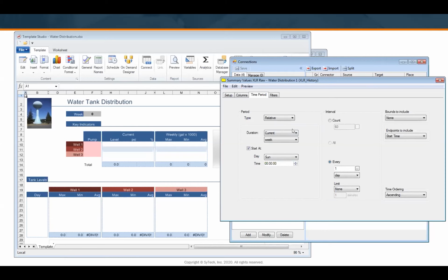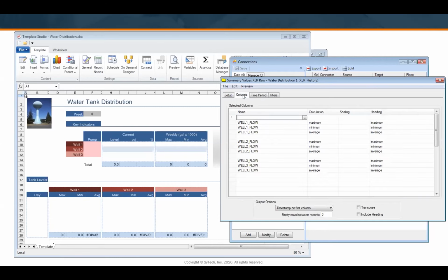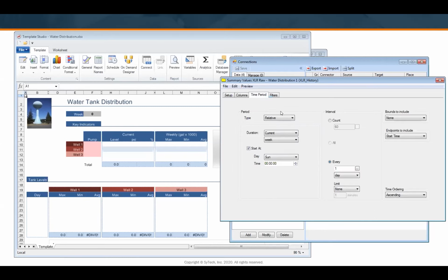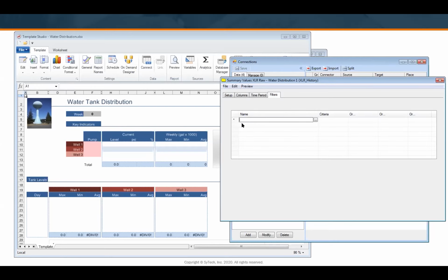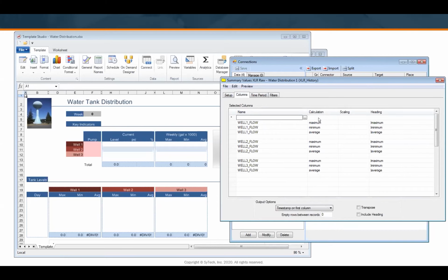Now, also, when you're calculating min, max, and averages, the worst thing you want is to include values when your pump wasn't running, because everything's going to come out ambient. So you can go in here and say, only perform these calculations when my pump is running, or my machine is running, or my temperature is greater than 30 degrees, just to eliminate some of that background noise that can distort the metrics.